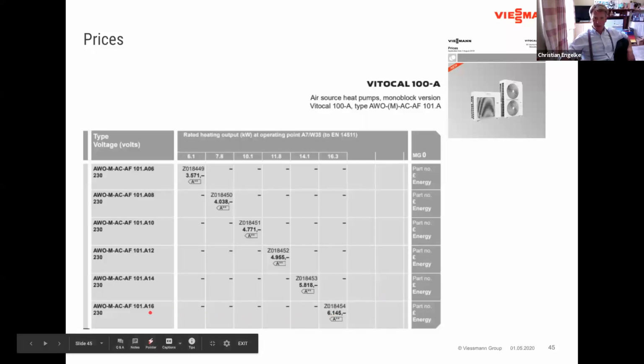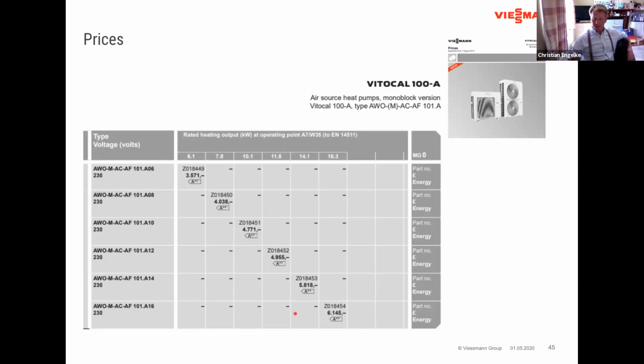Okay, so it's a 16 kilowatt model here, and it's 16 kilowatt at a 7-degree outside temperature, and the output will obviously drop gradually a bit the colder the conditions are. So let's say at -1 or -2 degrees, the output will be around 12.6 or 13 kilowatts. So yeah, that needs to be watched for. Does that answer your question there, Christopher?